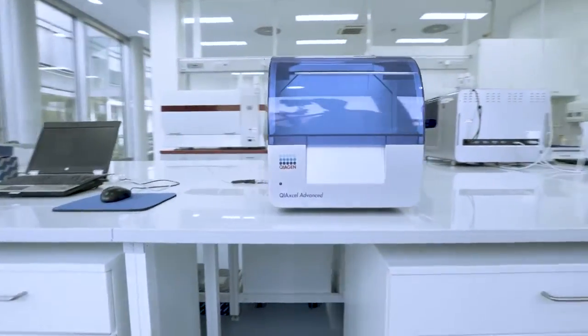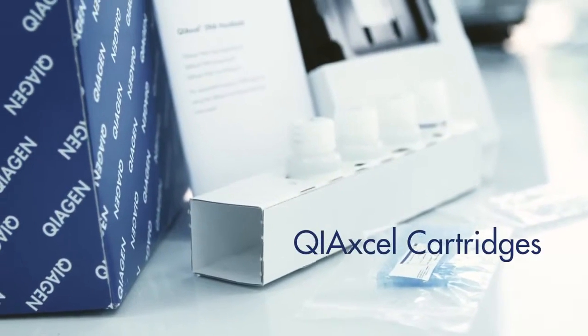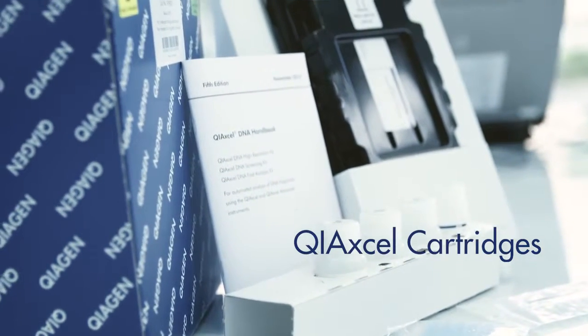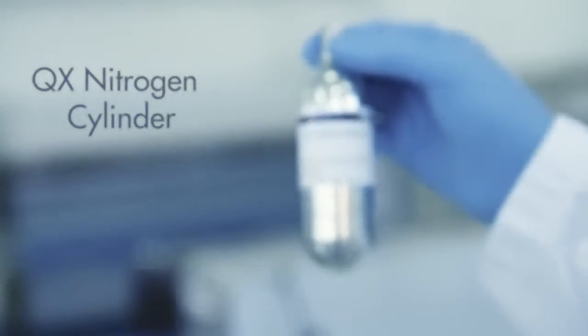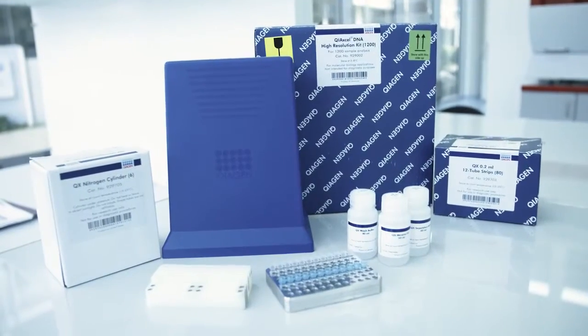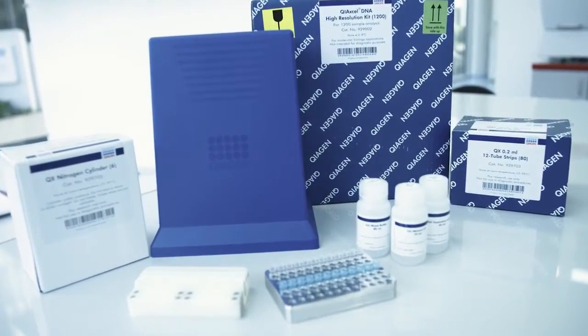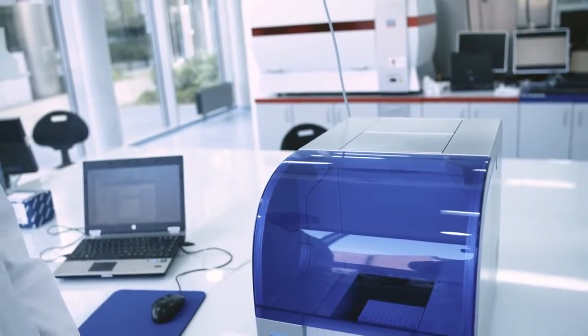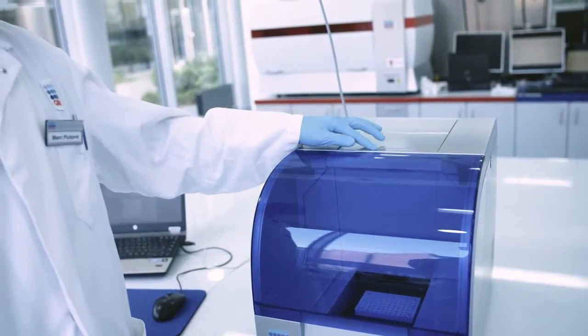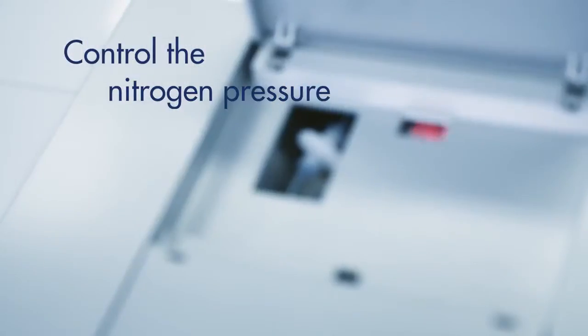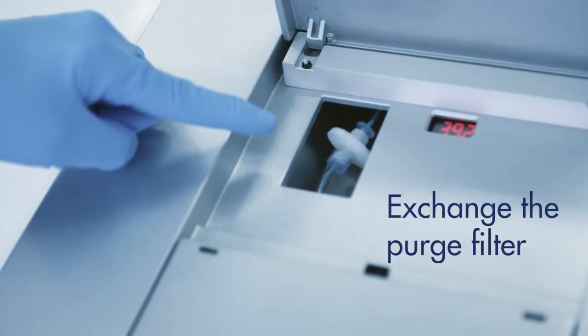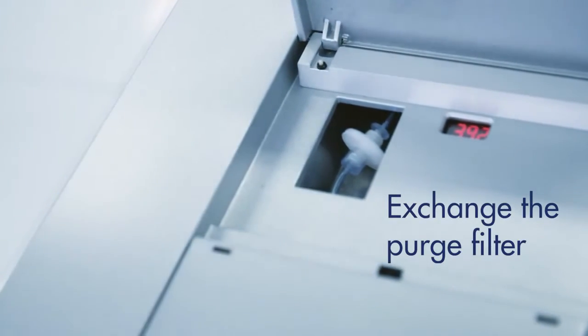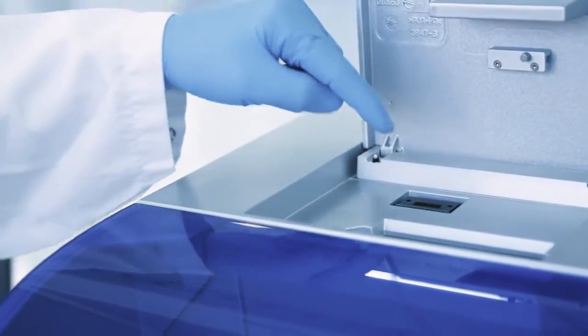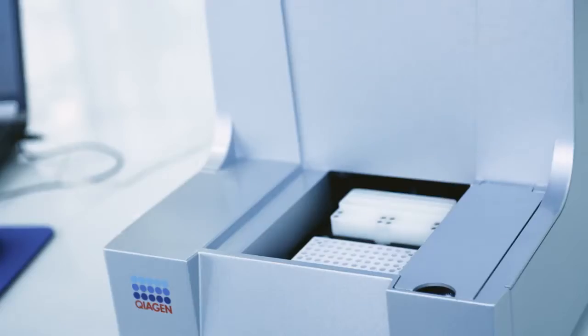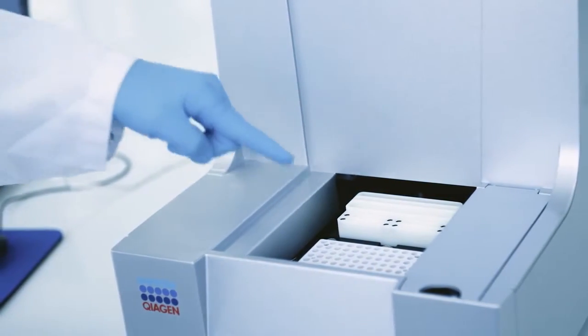To run QIAxcel Advanced, you will need QIAxcel cartridges that are specific for your applications and the QX nitrogen cylinder. You can analyze between 12 and 96 samples per run. At the top of the QIAxcel Advanced, users have access to control the nitrogen pressure and also to exchange the purge filter in case it needs to be replaced. Insert the QIAxcel cartridge and the smart key. Load the samples and buffer tray onto the work table.